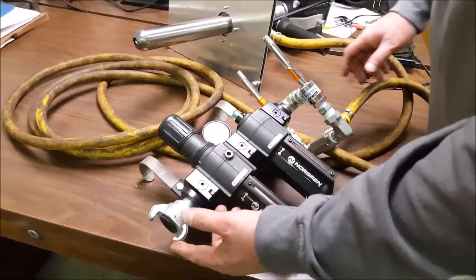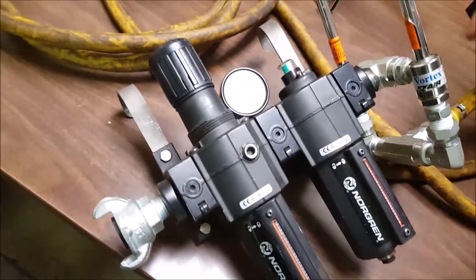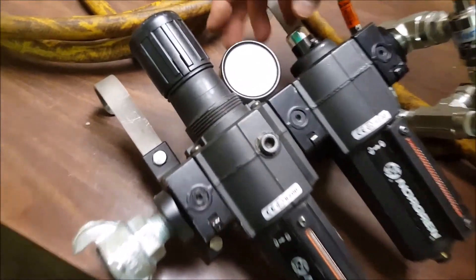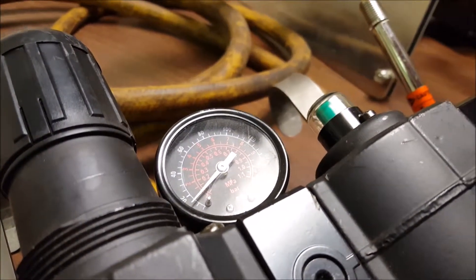When you hook your plant air up here, your Chicago fitting or whatever fitting you're going to use, you'll turn the air on and you want your regulator to show no less than 60 psi. That's what you recommend to keep the camera lens cool.